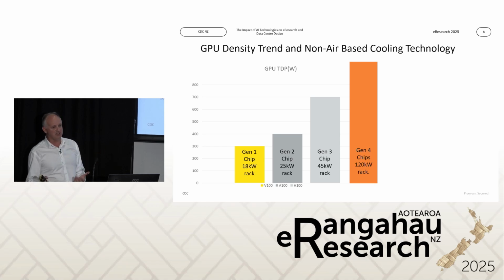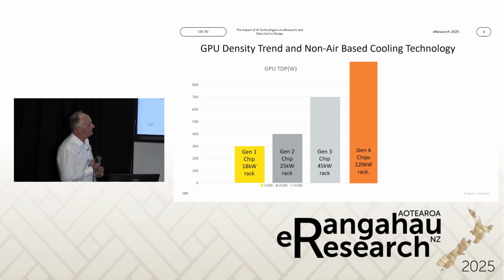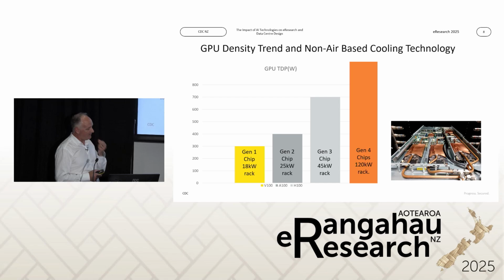If you put them into servers and fill up a rack with the V100s, you're talking about 18 kilowatts in a rack. If you pack the Blackwell chips into a rack, you get about 120 kilowatts. Some of that densification comes from changes in the processor, but a lot of it's actually coming from how we're cooling them. We're having to fundamentally change the way we look at cooling.